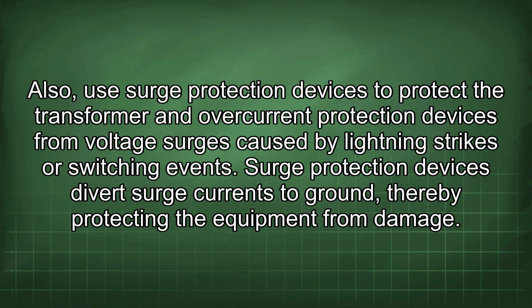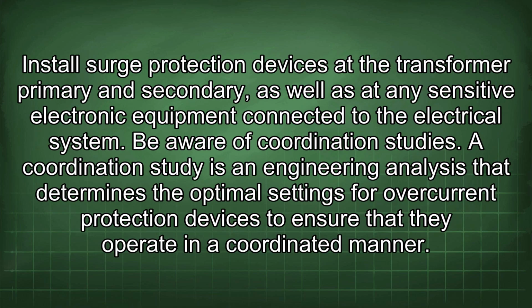Also, use surge protection devices to protect the transformer and overcurrent protection devices from voltage surges caused by lightning strikes or switching events. Surge protection devices divert surge currents to ground, thereby protecting the equipment from damage. Install surge protection devices at the transformer primary and secondary, as well as at any sensitive electronic equipment connected to the electrical system. Be aware of coordination studies.